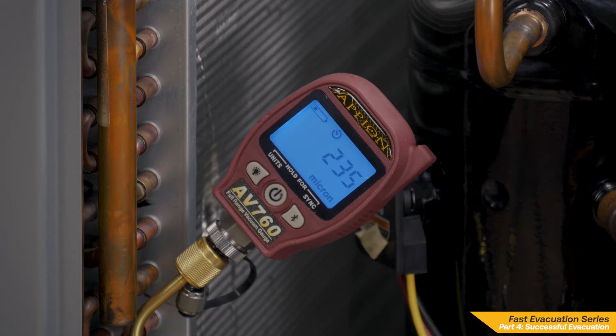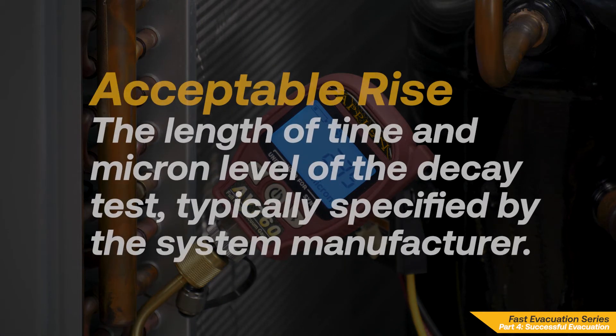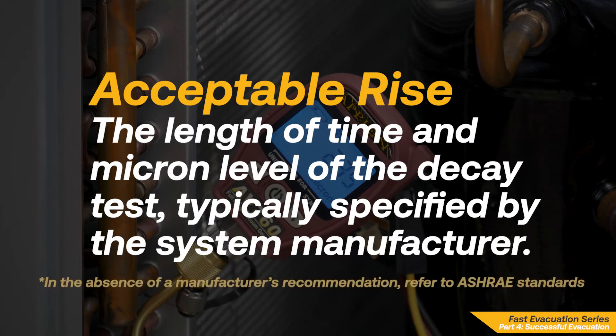During this window, the vacuum level is allowed to rise up to a specified level. The length of time and micron level, typically specified by the system manufacturer, are jointly referred to as the acceptable rise. In the absence of a manufacturer's recommendation, refer to ASHRAE standards.